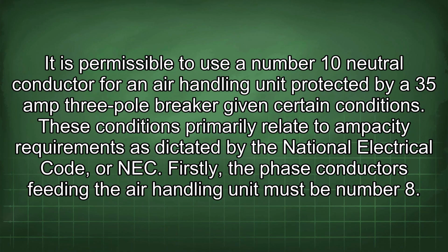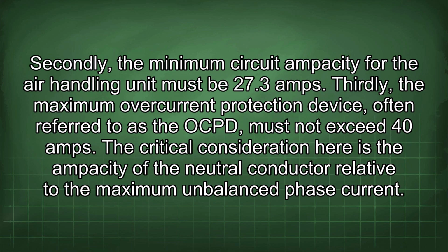It is permissible to use a number 10 neutral conductor for an air handling unit protected by a 35 amp 3-pole breaker given certain conditions. These conditions primarily relate to ampacity requirements as dictated by the National Electrical Code, or NEC. Firstly, the phase conductors feeding the air handling unit must be number 8. Secondly, the minimum circuit ampacity for the air handling unit must be 27.3 amps. Thirdly, the maximum overcurrent protection device, often referred to as the OCPD, must not exceed 40 amps.